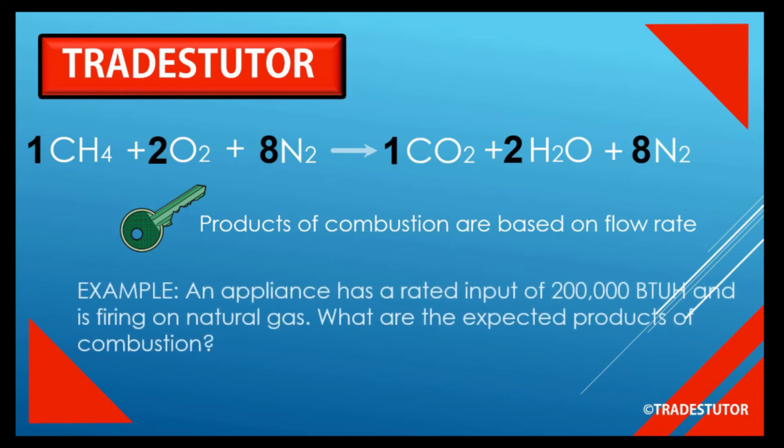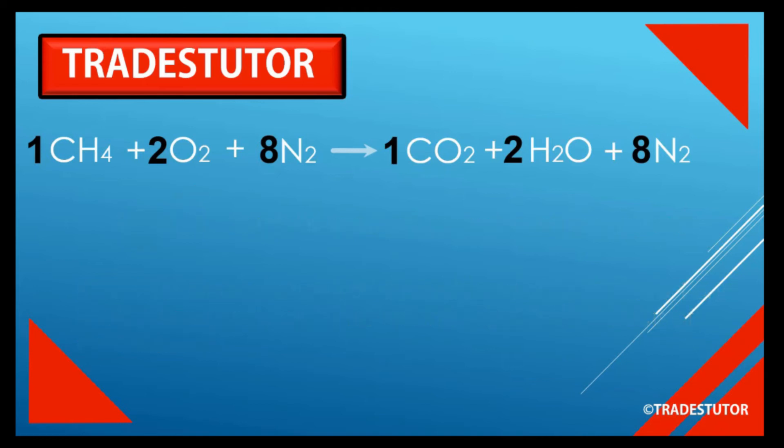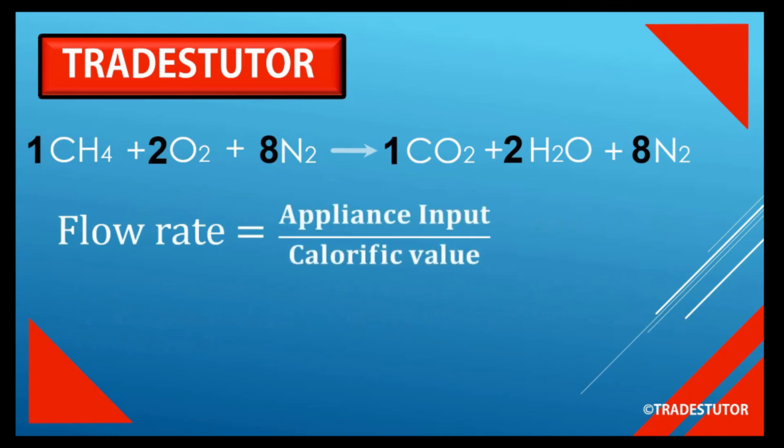An appliance has a rated input of 200,000 BTUs per hour and is firing on natural gas. What are the expected products of combustion? According to that key, the first thing we've got to do is find a flow rate. The formula is: flow rate equals appliance input divided by the calorific value of the gas being used.